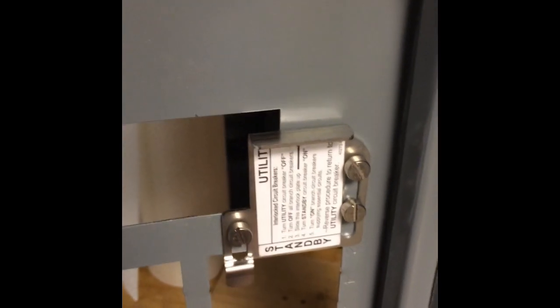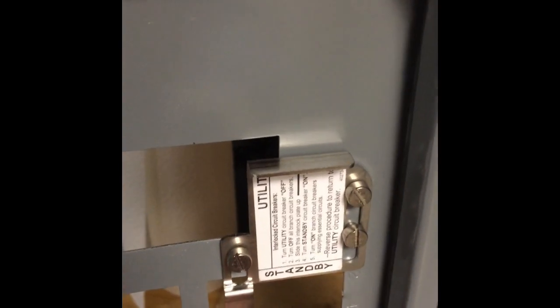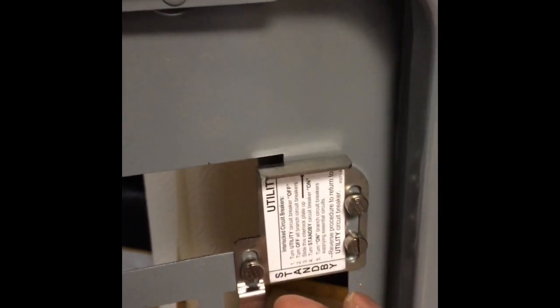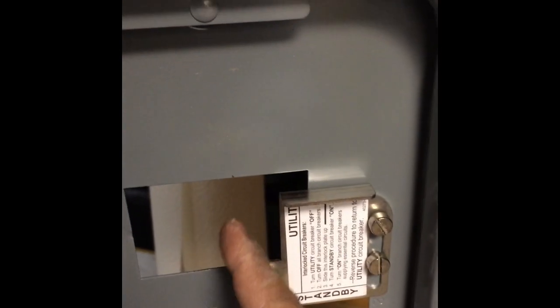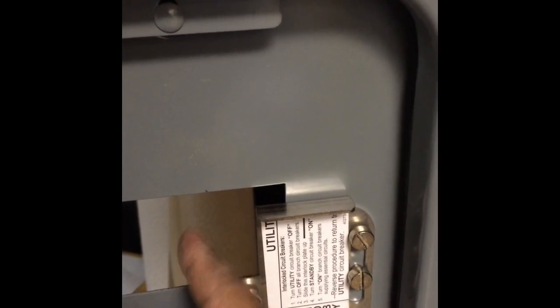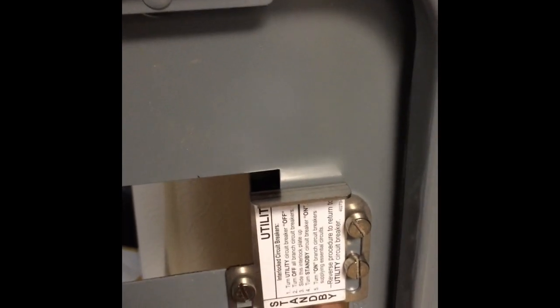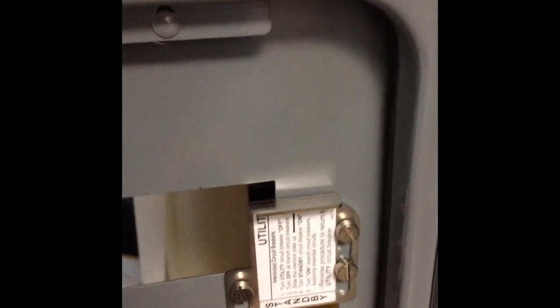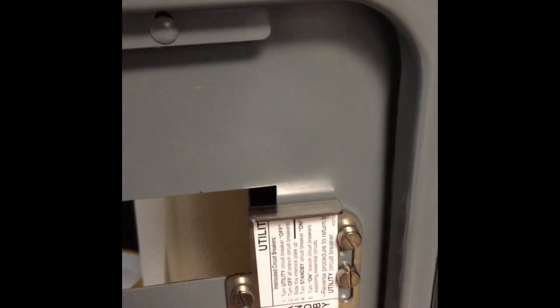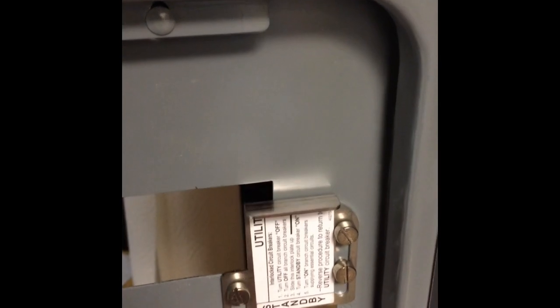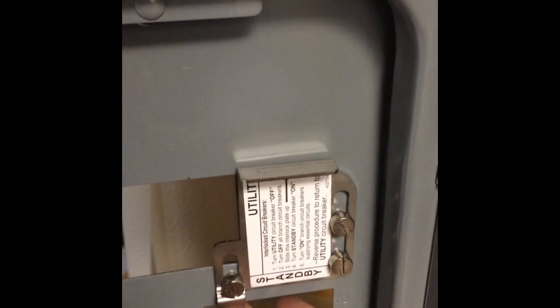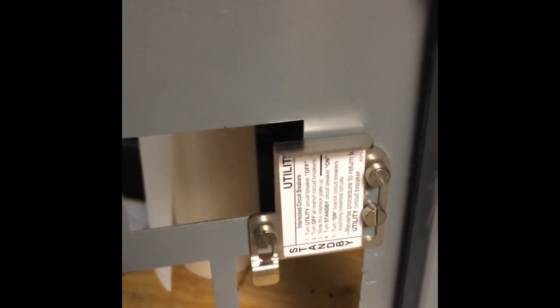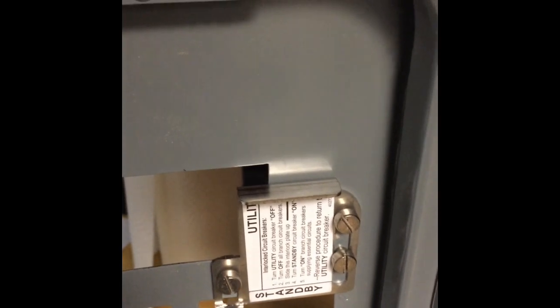Okay, this is the interlock actually installed. As you can see it slides freely. The whole idea is once it's on the panel it'll interlock the main breaker that's here with the generator breaker that's here, making it so that if one is on the other has to be off. Alright, so let's put the panel, let's put the cover on the panel and see how it works.